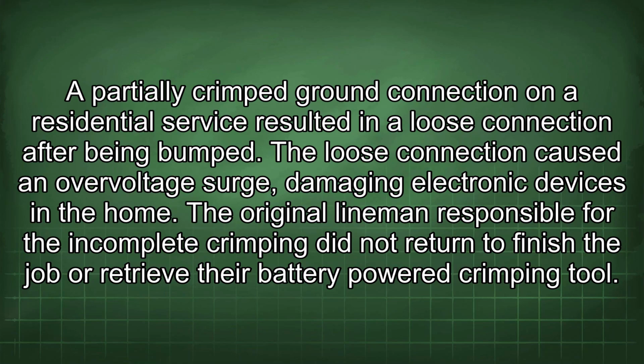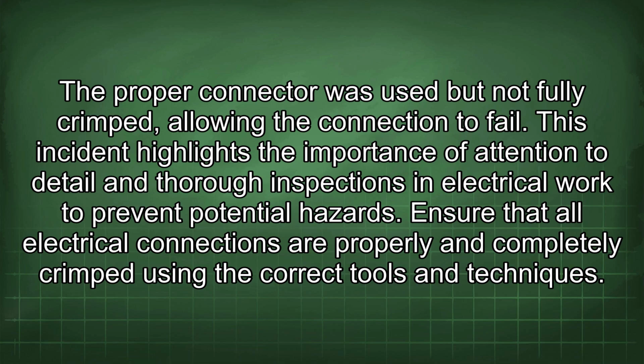A partially crimped ground connection on a residential service resulted in a loose connection after being bumped. The loose connection caused an overvoltage surge, damaging electronic devices in the home. The original lineman responsible for the incomplete crimping did not return to finish the job or retrieve their battery-powered crimping tool. The proper connector was used but not fully crimped, allowing the connection to fail.